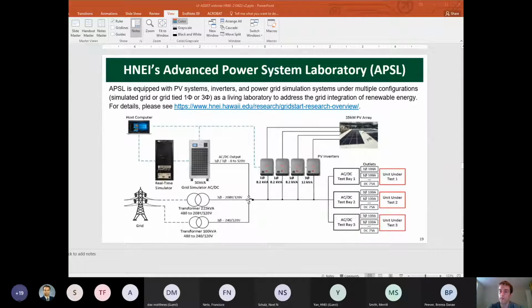And then more specifically on the voltage rise issue, at least in Hawaii and I'm assuming in other states, there are some settings in these smart inverters to do volt var compensation. At least in Hawaii, there's a dead band around the nominal voltage range, so that in normal operation you're not going to be injecting or sinking reactive power. But when voltage starts to become out of bounds, high or low, then it injects or sinks reactive power to help with that voltage rise and sink issue. That is not coordinated, so it's just a local decision of the individual inverter. There's no coordination or optimal power flow among inverters really in the field.